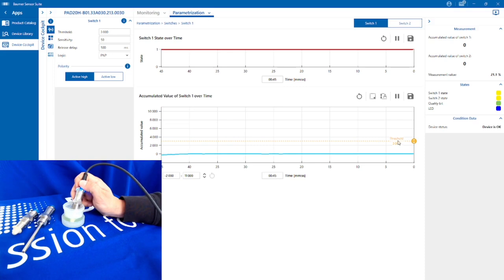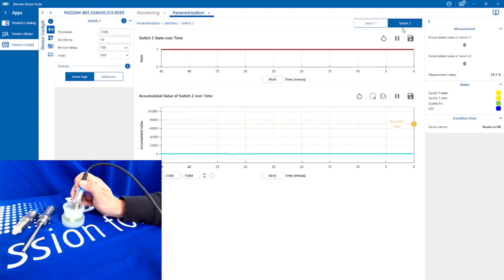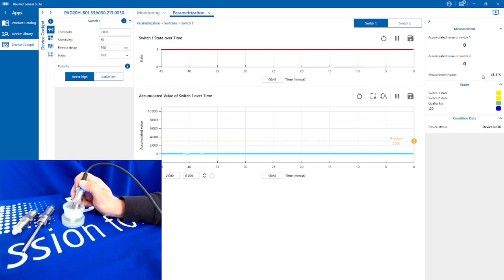Switch output one I've got a threshold set of 3000. I can switch to switch two and I've actually set that at 7000 just to show the difference. At the moment both switches are on because they're in a safe state and I've decided that I want this sensor to be active high, so when it's immersed in a fluid I get a nice output.